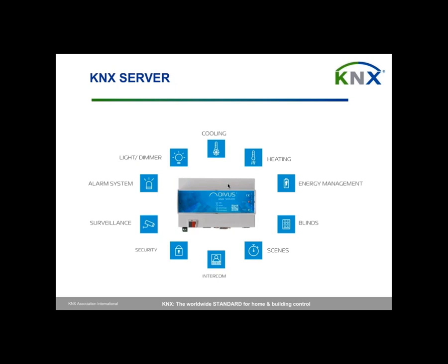Otherwise, using just a gateway, because some of our customers ask, okay, can I use a gateway? Yes, you can do that. But you will not have the chance to save any data or control any data. You will just send telegrams to the bus, and you will just get telegrams from the bus. That's all. But we want to go one step further with a KNX server. With a KNX server, we can control cooling, heating, energy, blinds, scenes, intercom, also the cameras, the security of the building or house, alarms, and so on.